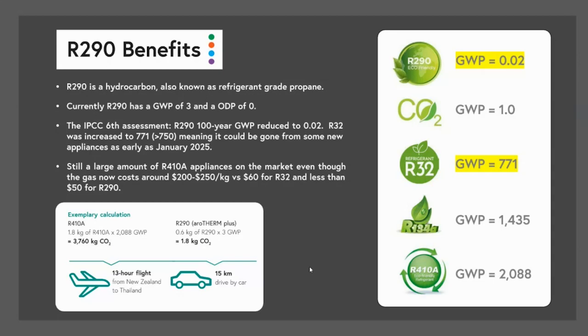But the interesting one is R32. So, the current industry standard, R32, pretty much every monoblock heat pump on the market is running this. You name a manufacturer, that's what they've got right now. And they increased that GWP rating to 771. So that is greater than the 750 mark that we talked about on the slide before. It means that most appliances running R32 by the 1st of January 2025 will be non-compliant and can no longer be sold into markets. Now that is assuming that this all goes through and it stays as the plan.